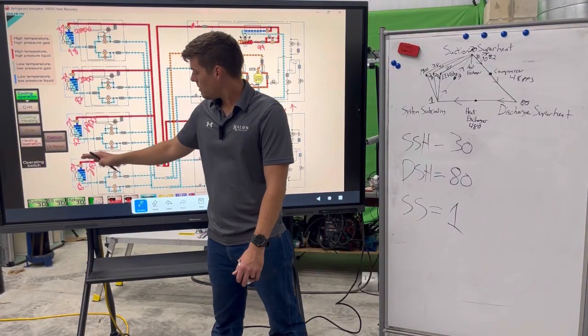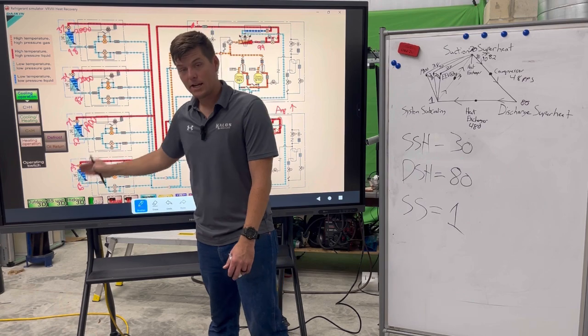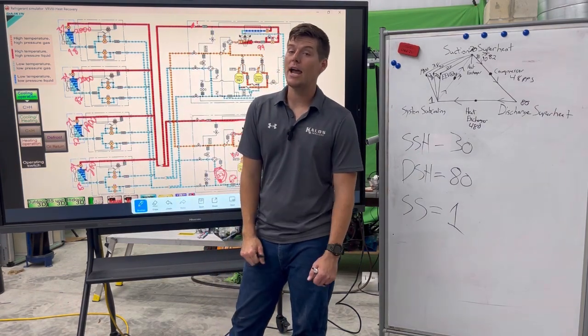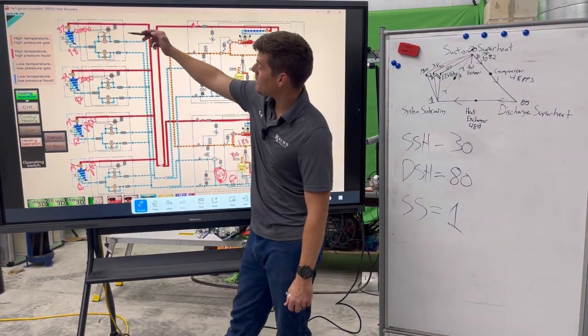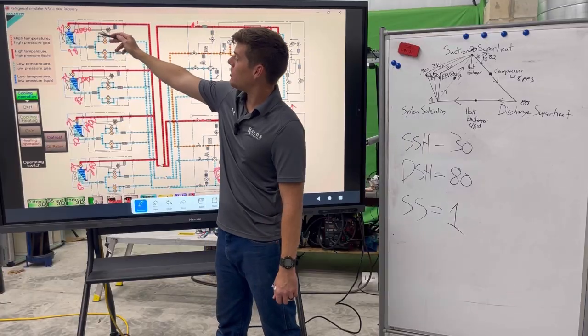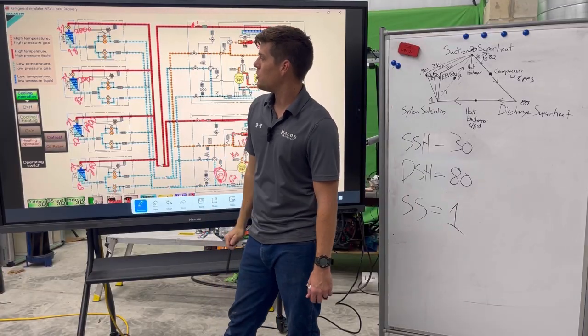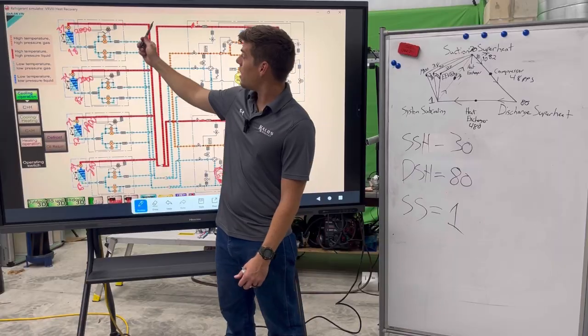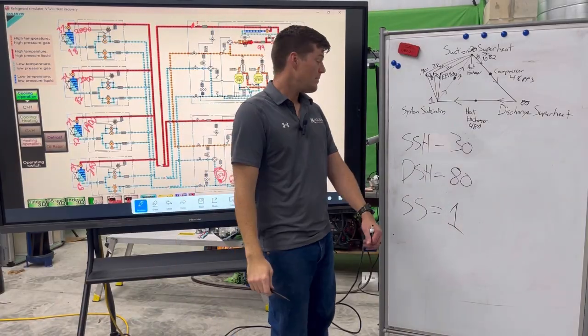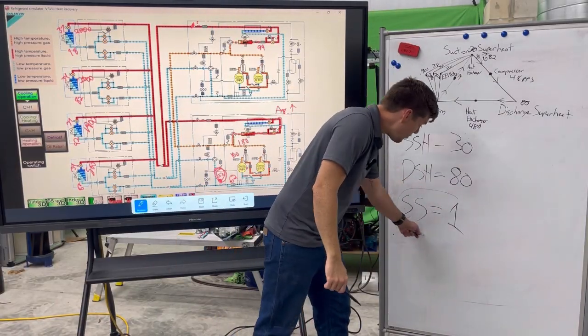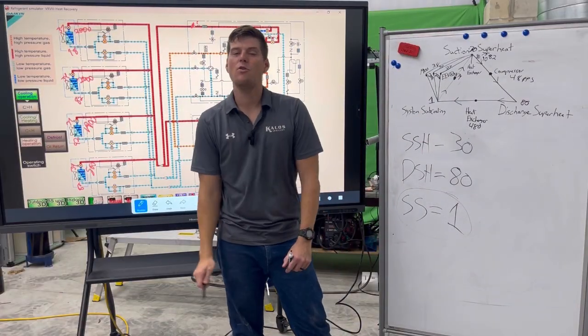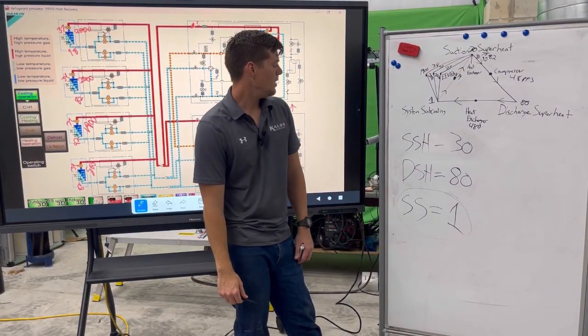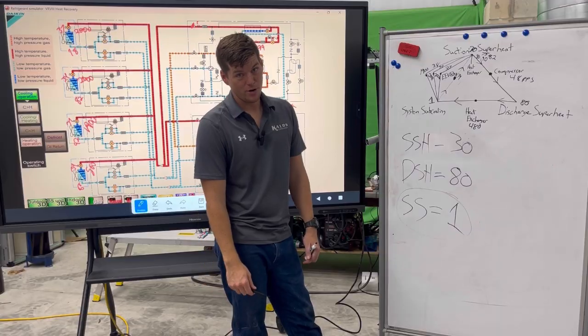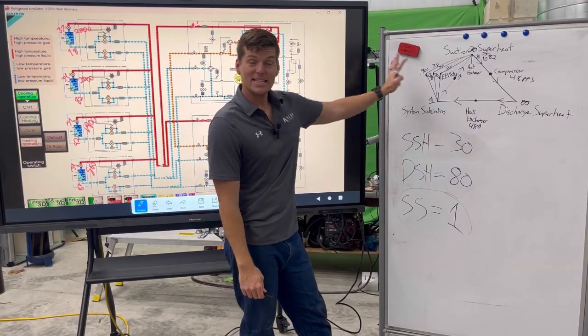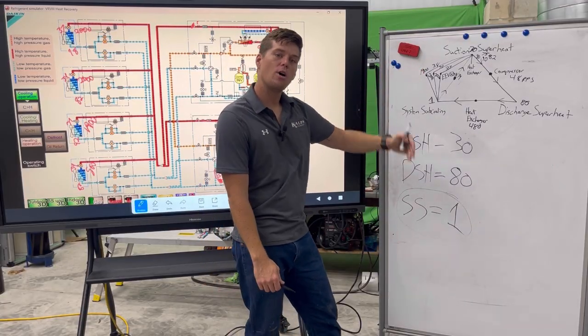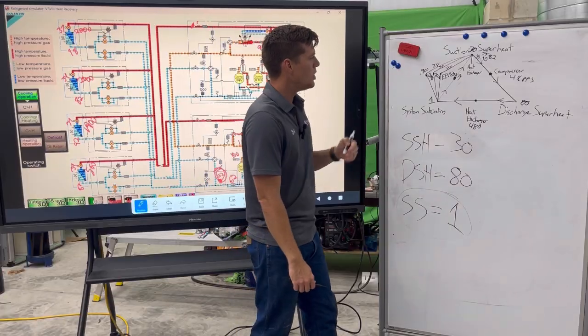Now again, this valve is going to open up more because it's not getting enough refrigerant. Indoor units are looking for what? A 9 degree superheat across them. So if I'm not metering refrigerant and it's saying, give me everything you've got, and I'm not hitting my 9 degree superheat, well, this tells me that I'm not getting enough liquid to my valves. And I already knew that because I have a 1 degree subcooling on the system. 1 degree subcooling doesn't go very far with 4 indoor units. This is getting messy, but you can see how we're unpacking this problem slowly but surely.